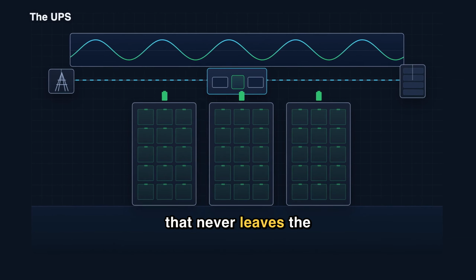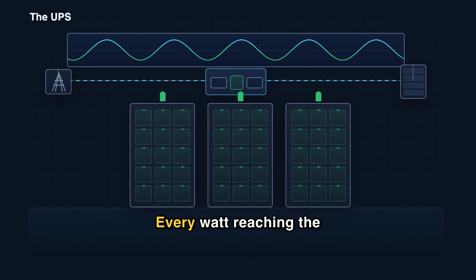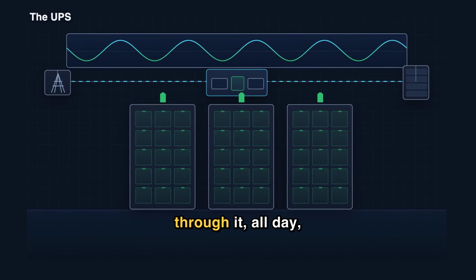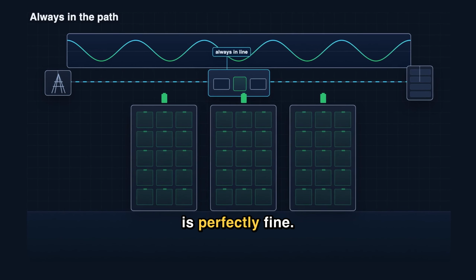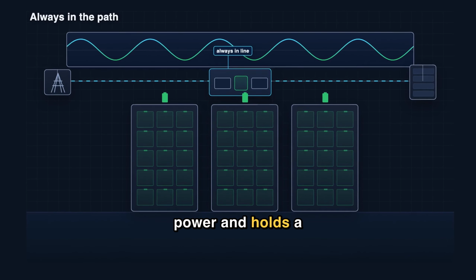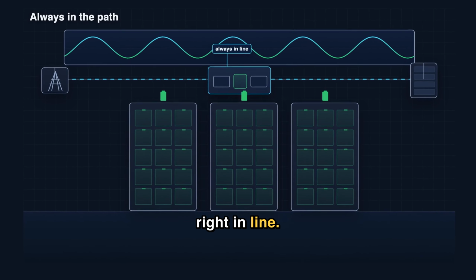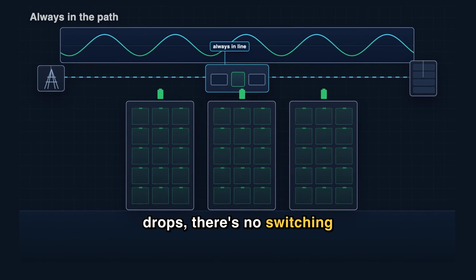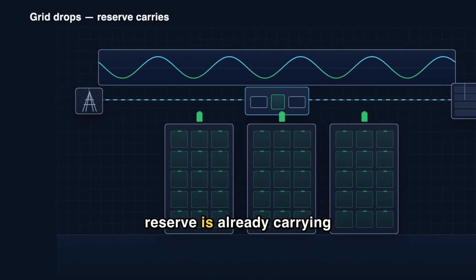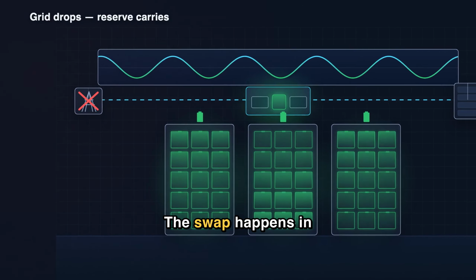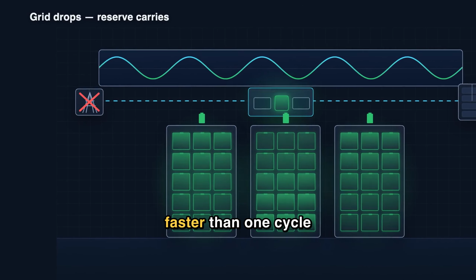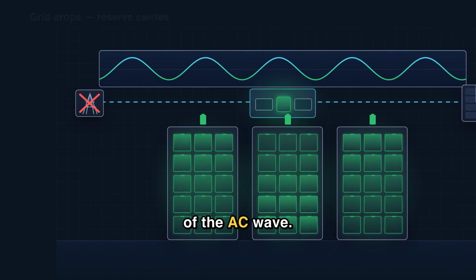Start with the piece that never leaves the path, the UPS. Every watt reaching the servers already flows through it, all day, even when the grid is perfectly fine. It cleans up the power and holds a reserve of stored energy right in line. So when the grid drops, there's no switching moment to survive. The reserve is already carrying the load. The swap happens in under 10 milliseconds, faster than one cycle of the alternating current wave.